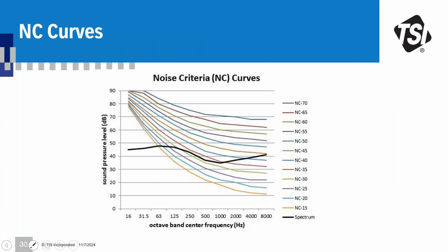And that's where we get into the NC curves, right? NC curves, the noise criterion curves, are another option to display records of noise behavior in a certain room environment, right? So the NC curve has a spectrum of frequencies, and this is a single number NC standard that allows you to effectively determine how loud your room is. So if you apply the NC25 to your meter, anything below the NC25 will not be heard if that's your standard, right? So these lines are standardized, and you take measurements with SoundPro to compare against the standard, right?